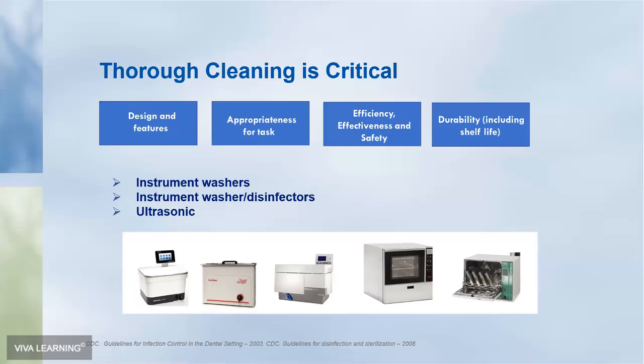For both types, washers and washer disinfectors, hot air drying occurs in the device. So it means when you take it out, the device has been rinsed, it's been cleaned, it's been rinsed again, and it's been dried. So there's no requirement to dry it. In the case again of the washer disinfector, you've also reduced the microbial load.